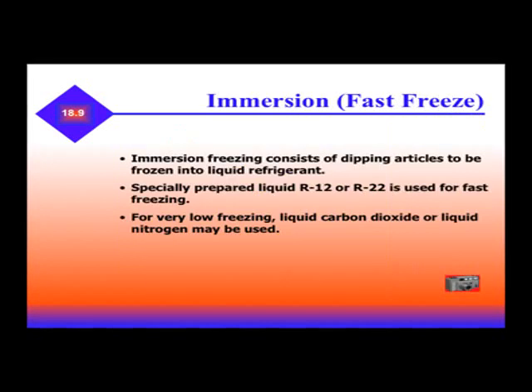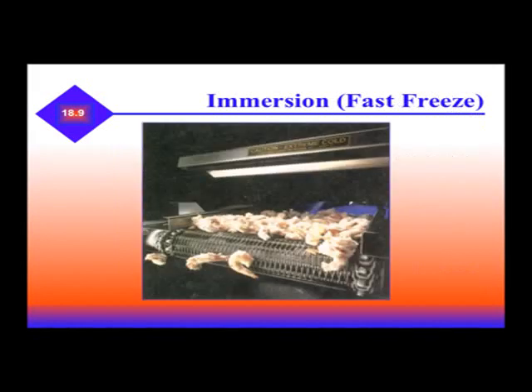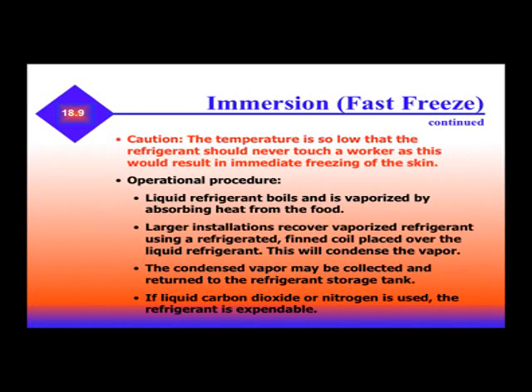Immersion freezing is considered fast-freeze freezing. It consists of dipping articles to be frozen into a liquid refrigerant. Specially prepared liquid R12 or R22 is used for fast freezing. The temperature is so low that this refrigerant should never touch a worker, as this would result in immediate freezing of the skin. Liquid refrigerant boils and is vaporized by absorbing heat from the food. Larger installations recover the vaporized refrigerant using a refrigerated fin coil placed on the liquid refrigerant, which will condense the vapor. The condensed vapor may be collected and returned to the refrigerant storage tank.